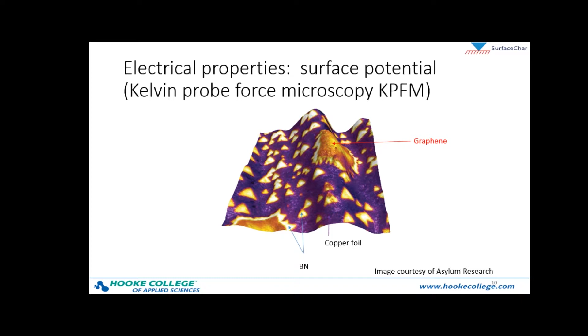Here is an example of a KPFM image. The KPFM signal has been overlaid or painted onto the topography, so we can see the 3D topography here, and the coloring is actually from the KPFM signal. This is a copper foil substrate that had flakes of both boron nitride and graphene. These flakes are only 1 atom thick, and so they were impossible to resolve in the topography channel alone. But by looking at the KPFM signal, we can see that the graphene flake has a different orange contrast compared to the bright white contrast of the boron nitride flake. And so mapping this tip sample potential easily differentiates these two materials.